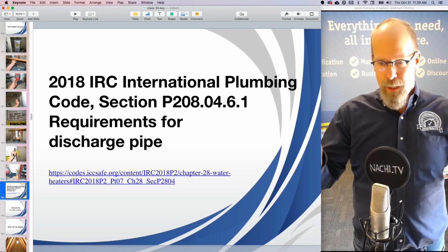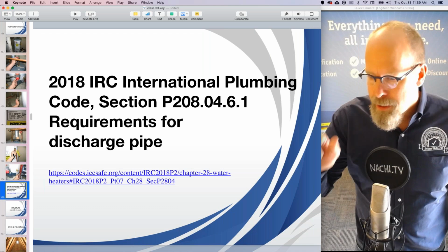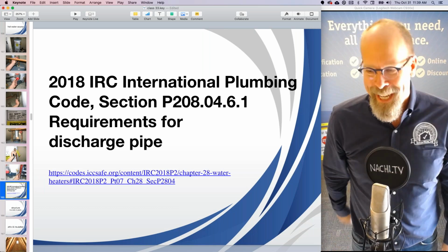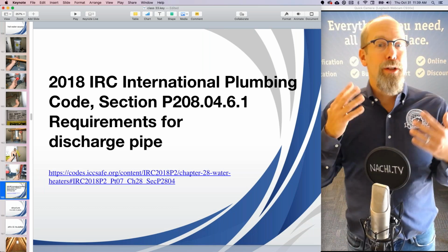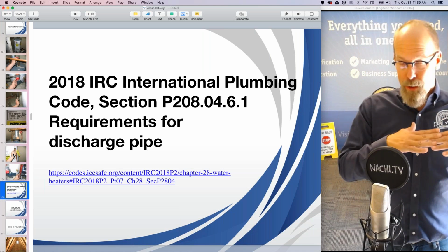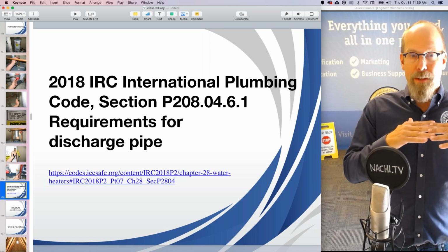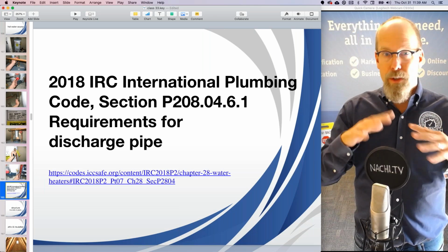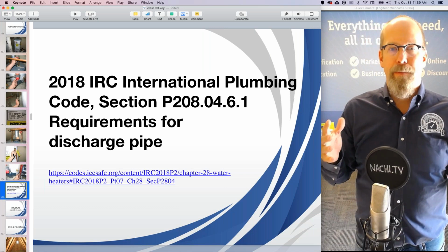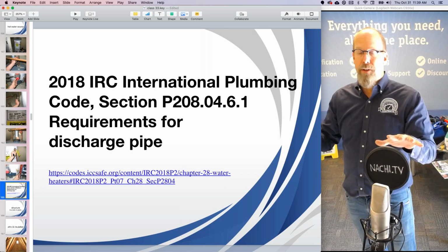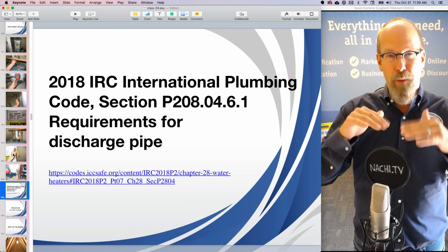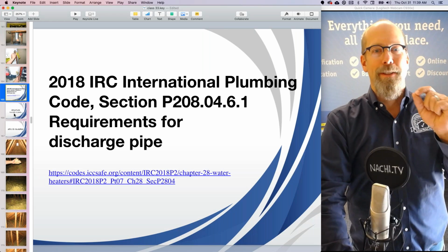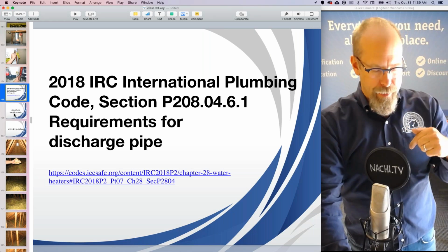Where's that? In the latest International Residential Code, section P2804.6.1. I wouldn't refer to code, but I would use code, just like you use InterNACHI's free online courses as a foundation upon which to build a really good inspection process. So use these two. All of InterNACHI's courses are based upon standards. If you take the courses, that's fine, but if you wanted to look at the actual code, it's available to you. So there's 14 things that the TPR valve needs to comply with.